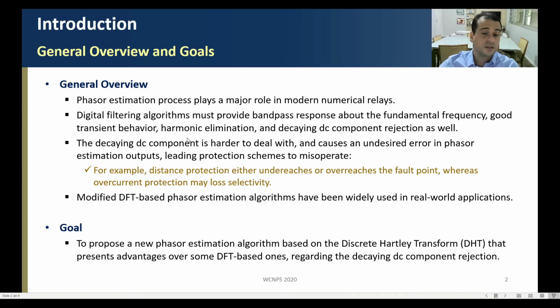The decaying DC component is harder to deal with, and it causes an undesirable error in phasor estimation outputs, leading protection schemes to misoperate. For example, distance protection either underreaches or overreaches the fault point, whereas overcurrent protection may lose selectivity.